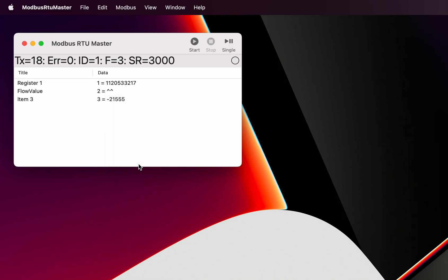In this case 64 is grayed out because we've only got three 16-bit registers established in here, so there's not a total of 64 bits in here. We can, for example, set that to use 32 bits, and you can notice that what you see in this line now is actually made up out of the contents of those two 16-bit registers. You can see these two carets here, they're pointing towards that, telling you that that value from this register is actually used to interpret what's shown here.